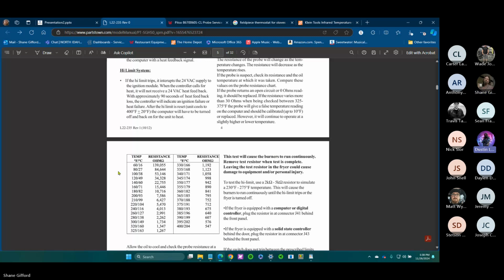Even if it's just room temperature, yep. I've had guys say, why didn't you check the temp probe? Well, my thermometer doesn't go that high. Just shut it down for a while, or if it's in the middle of a bad time, schedule to come back before they open. And that's the other thing about hot side: sometimes you have to get there before they open and be able to do all your tests and functions and everything else.